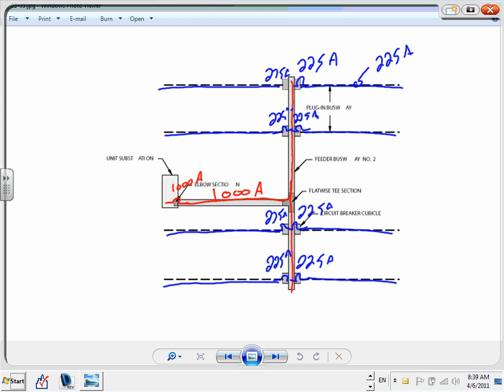If you came up with something different, based on my calculation the bus that we're going to have is 1,000 amp. If you were to run 800 out there, you'd have to put 800 on it. If you put an 800 overcurrent protection device here, yes, this has to be 800. Absolutely. The best thing when it comes to plug-in busways is to match the overcurrent protection device to the plug-in size, to the best of your ability.